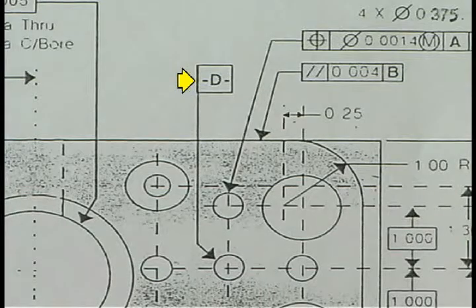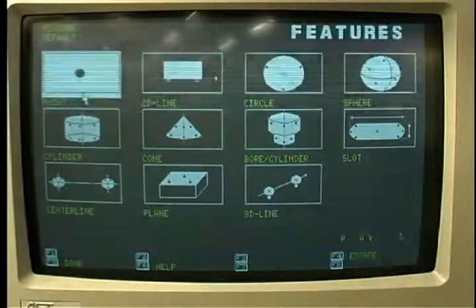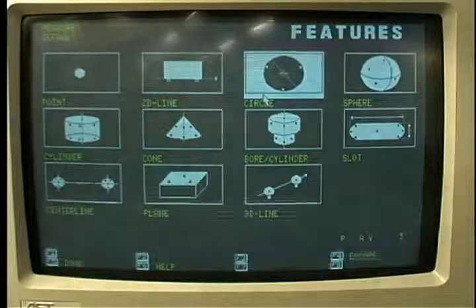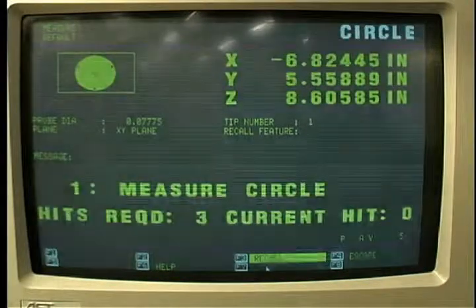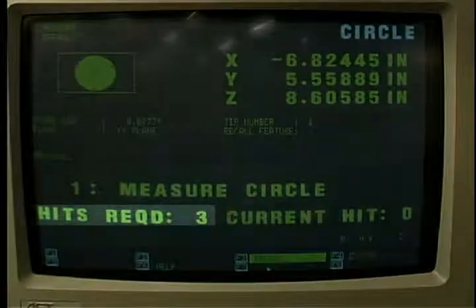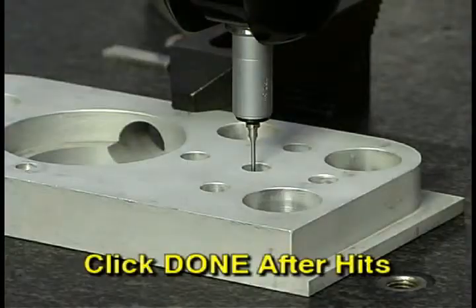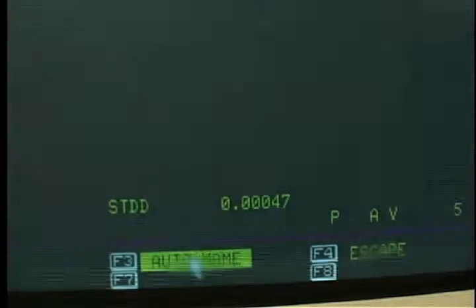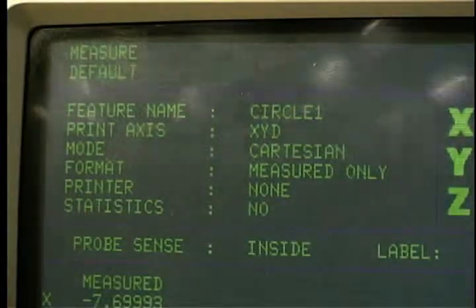The third axis to be established is Datum D. Select Measurements again. Since Datum D is the center of a hole, the circle selection is used. While three hits must be taken to locate the hole center, four are taken to get the standard deviation. Click Done to complete the calculation. After the hits are completed, check the deviation. Auto Name the feature and it will be Circle 1.